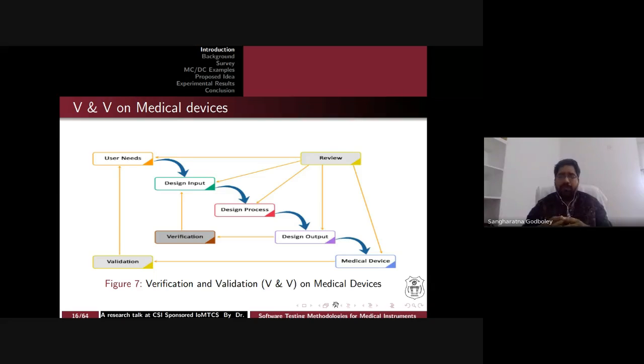You can see that we have user needs on top of this. So it usually looks like a waterfall model. If you have read a software engineering course, then you can see that this is a kind of waterfall model. But in verification, we are focusing on the design phase, before testing. If user needs are there, and you are trying to design those requirements, then design input will be the phase, then after that design process, then design output will come. After that, you have verification. Based on the design output, you are verifying it, again going back to design input. Then this makes one cycle for verification.